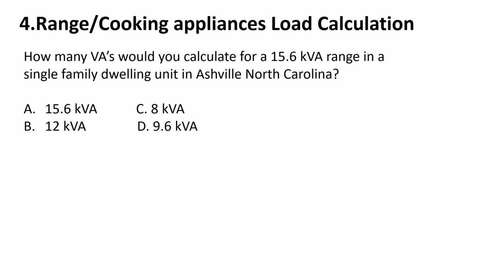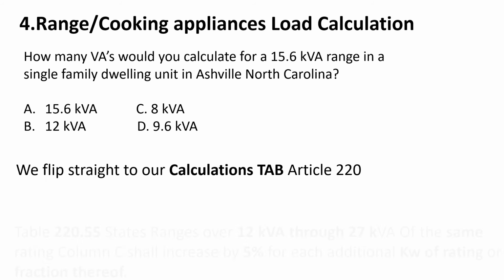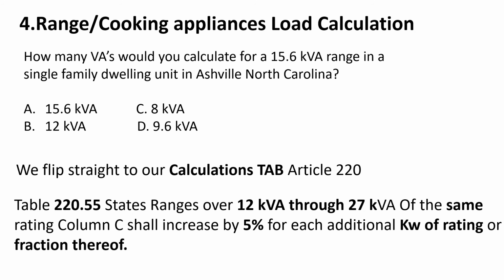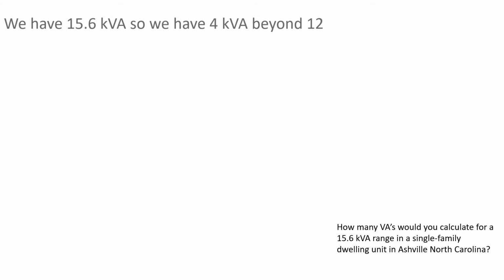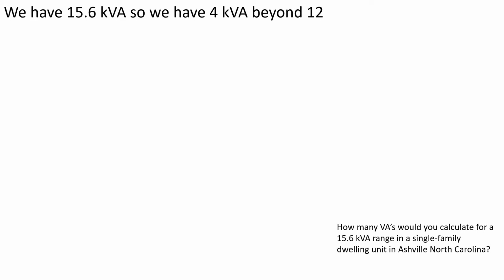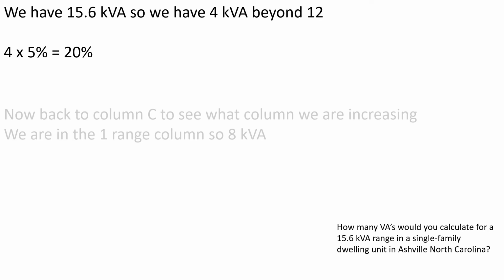How many VAs would you calculate for a 15.6 kVA range in a single-family dwelling unit in Asheville, North Carolina? We flip straight to our Calculations tab in Article 220. Table 220.55 states that ranges 12 kVA through 27 of the same rating shall be increased by 5%. We have 15.6 kVA, so we're going to be 4 kVA beyond 12 because we're going to round that 0.6 up. 4 multiplied by 5% equals 20%.